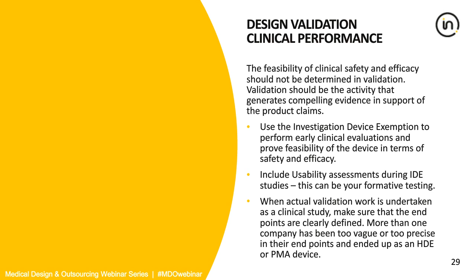When actual validation work is undertaken as part of the clinical study, make sure that you clearly define the endpoints on the study. What is it that's going to prove that you meet the requirements and you meet the user needs and that the product is safe and effective? More than one company has been either too vague or too prescriptive in their endpoints, and they either ended up not making the requirements as maybe a 510K, or it pushed them because they demonstrated that they had more risk than anticipated into a PMA or an HDE device. So be real careful when you're doing your clinical evaluation to assure that you've got the endpoints defined and you're confident that you'll achieve them.